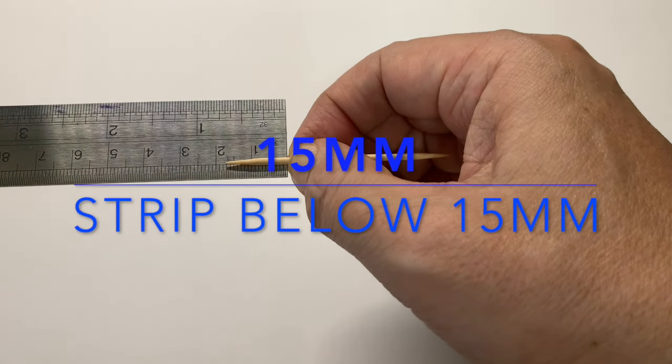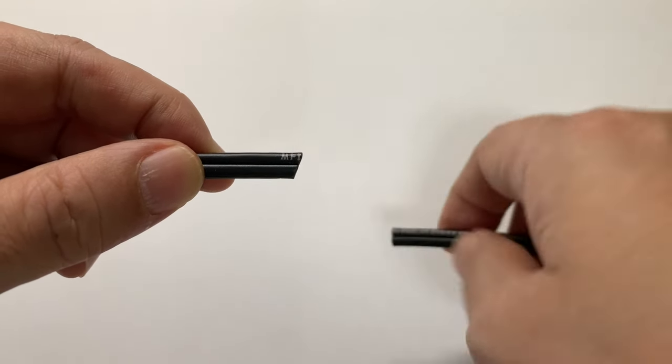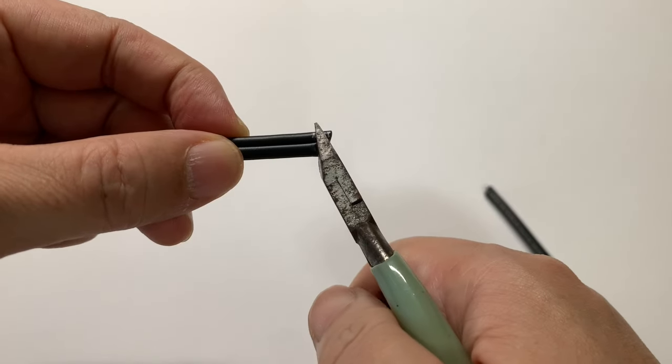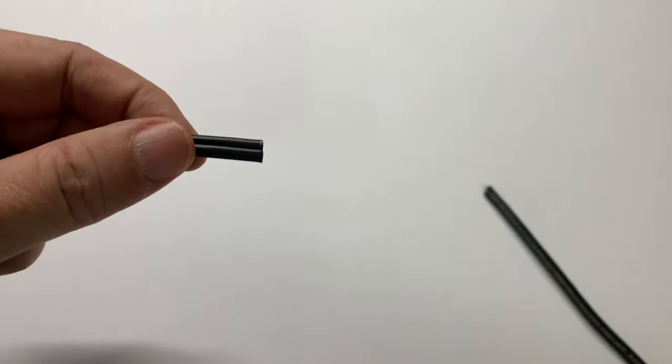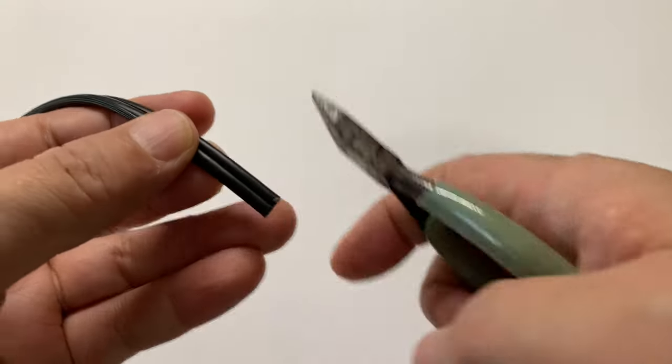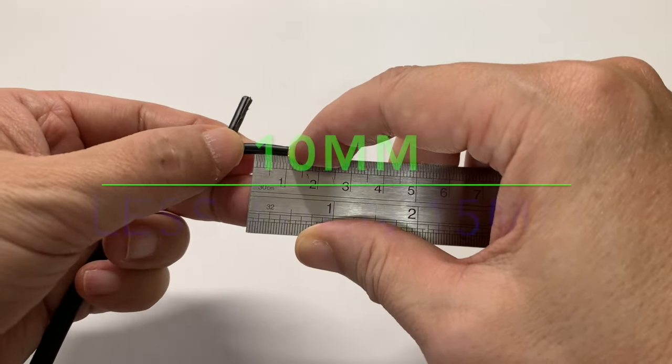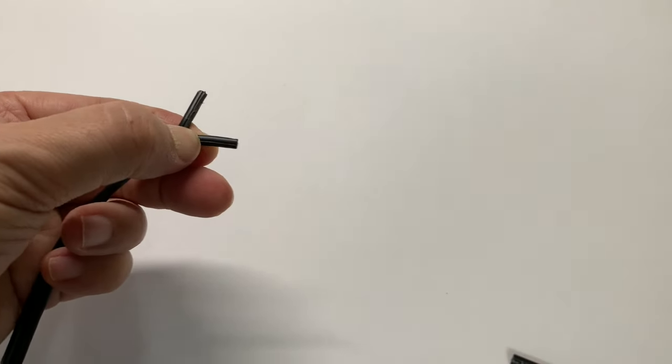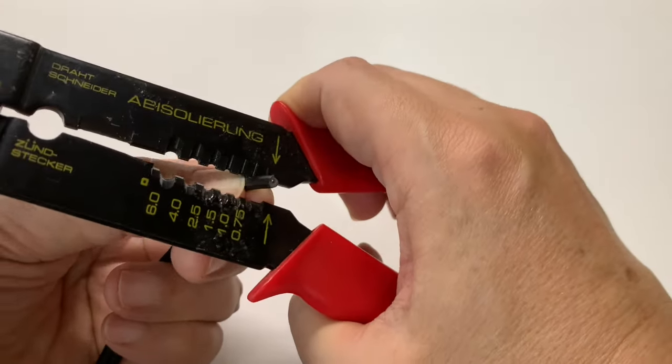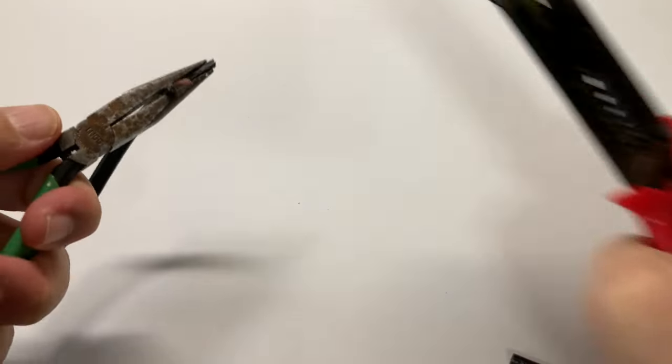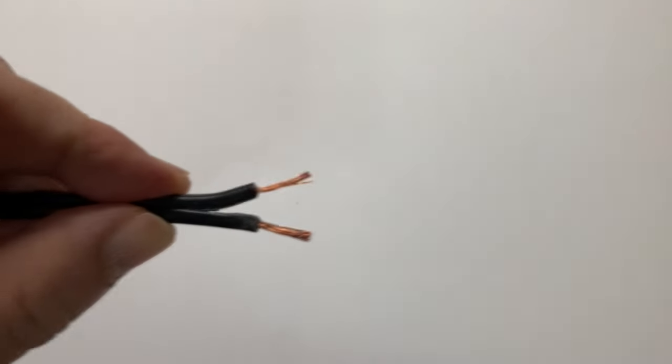Let's measure the depth to determine how long we should strip the wires to be spliced. The depth is around 15 millimeters, so the rule of thumb is to strip less than that. Make sure the tip of the pair of wires are cut flush to each other. I'll strip the wire to around 10 millimeters.